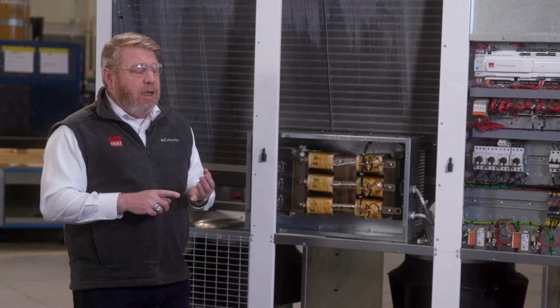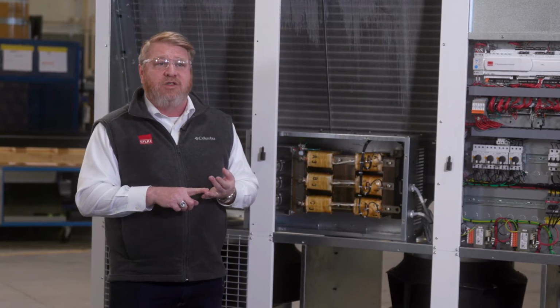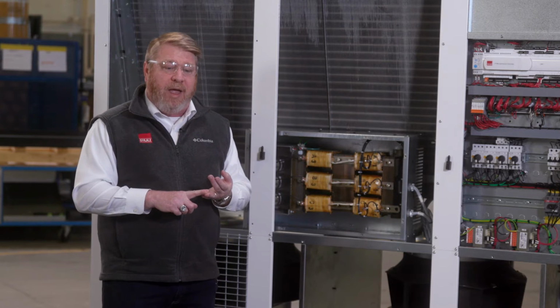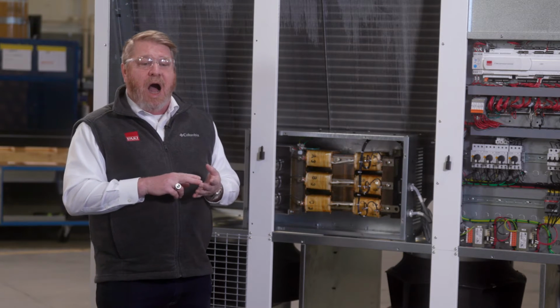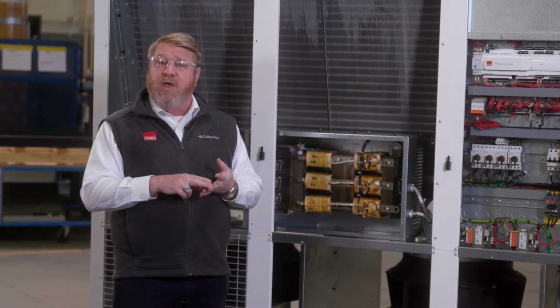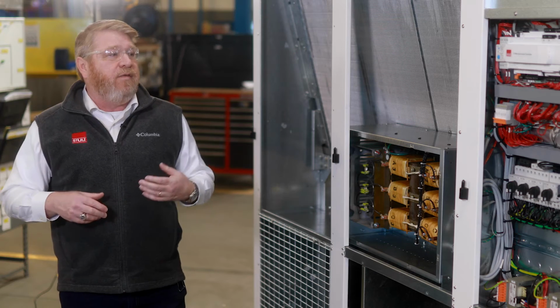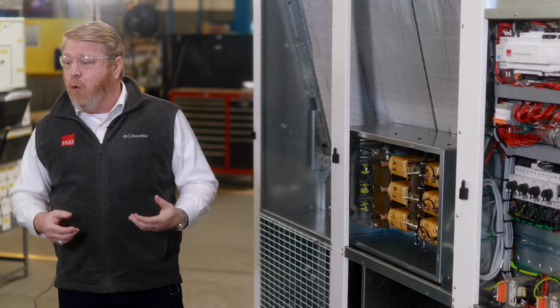The negative to that is if we have those additional signals being added to the sinusoidal power input, we expect to see things like increased peak current and greater temperature rises within the equipment. We can see higher electromagnetic emissions, and we can even see, at higher frequencies, core loss within the motor itself.